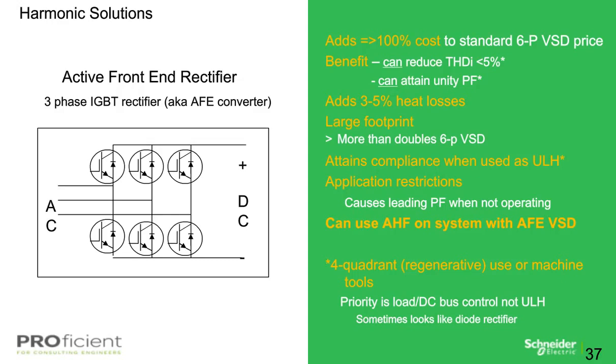And then, moving down to the far right of the slide, if the load is a constant torque application that has 100% torque required from 0 to 1% speed, or a regenerative load, i.e. a downhill conveyor or a production machine or equipment, the logic no longer manages the active front end to attain clean power. The logic is designed to maintain the DC bus capacitor voltage for optimal torque control of the load. Sometimes the input current can also look like a diode rectifier, and a 5% THDI is not attained. There has also been installation of this type of active front-end VFD without the input filters, which we'll discuss in the next couple slides in some detail, which causes higher voltage distortion.